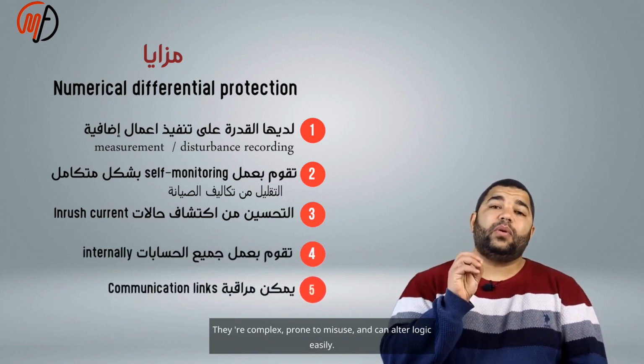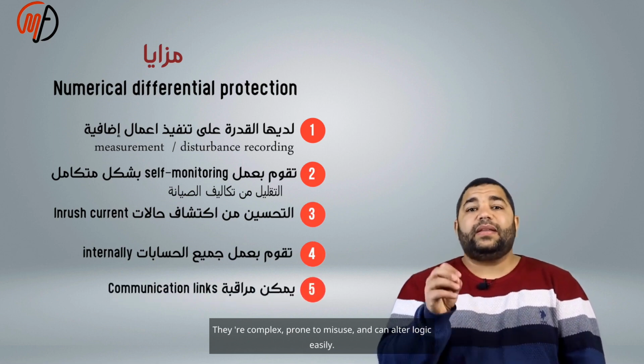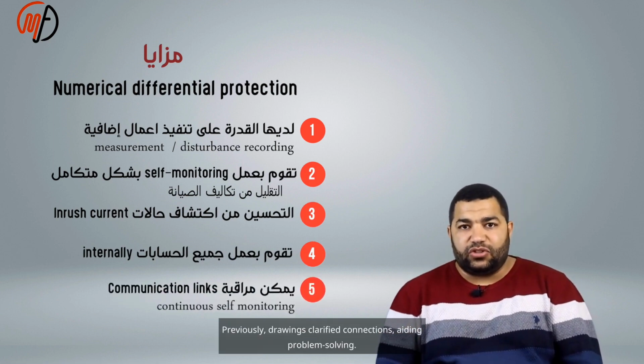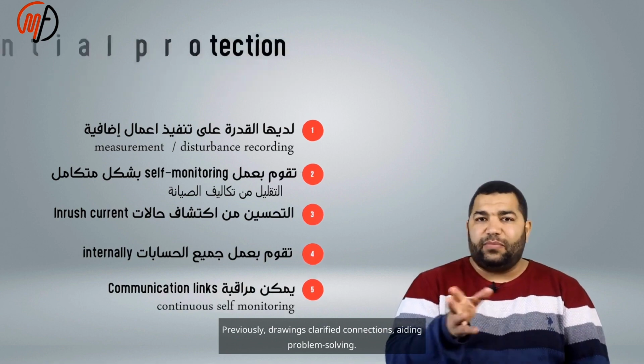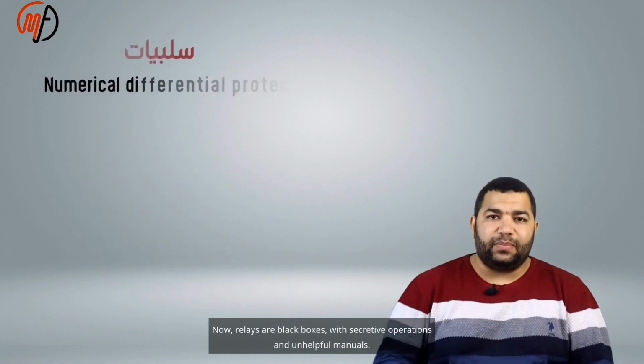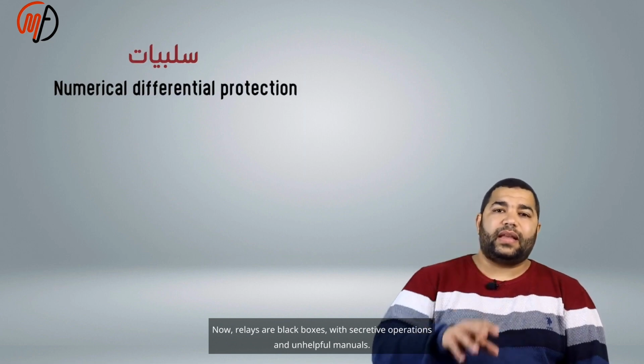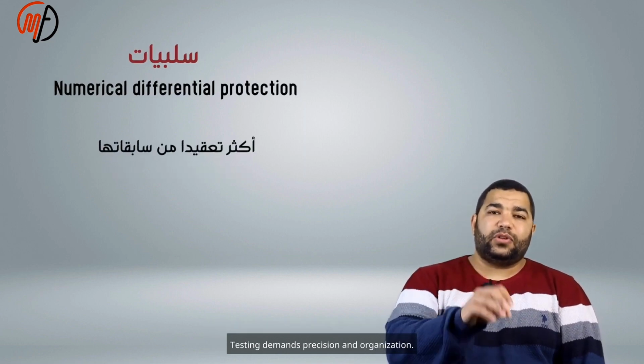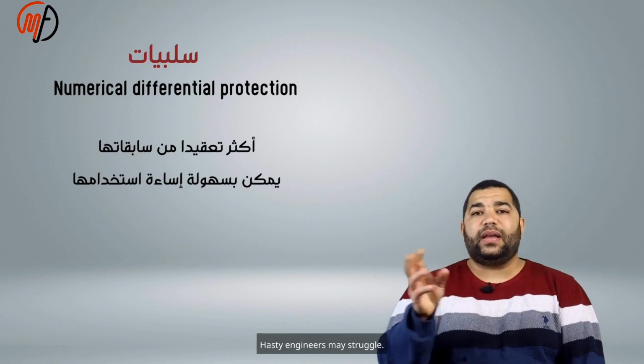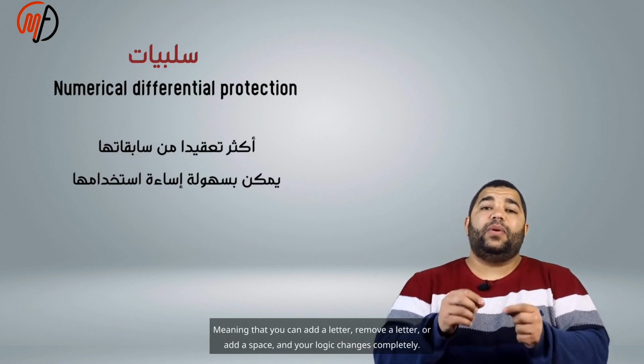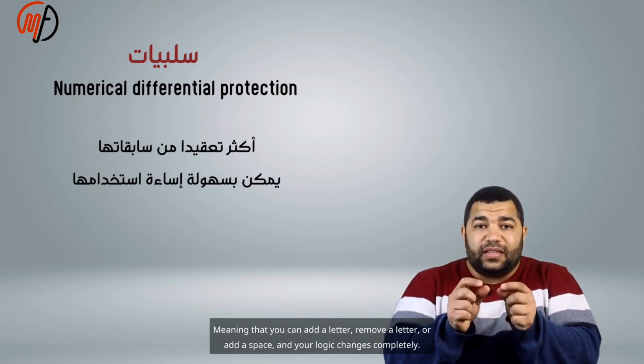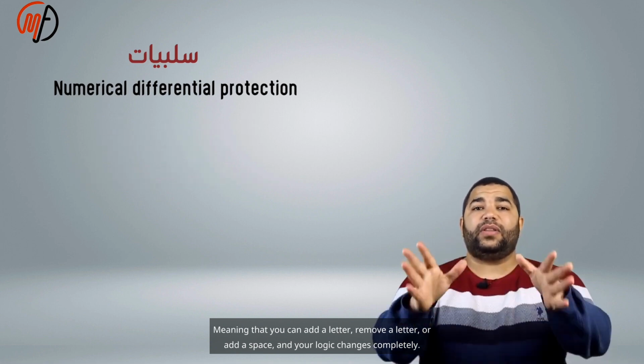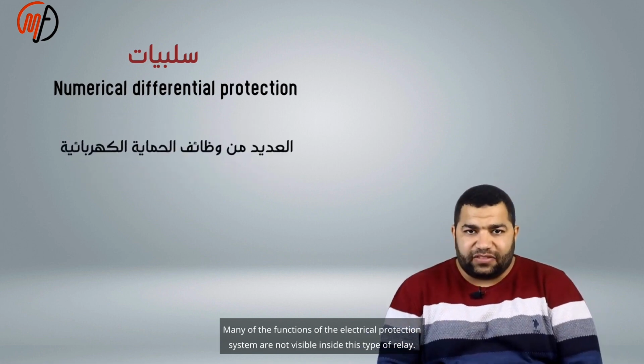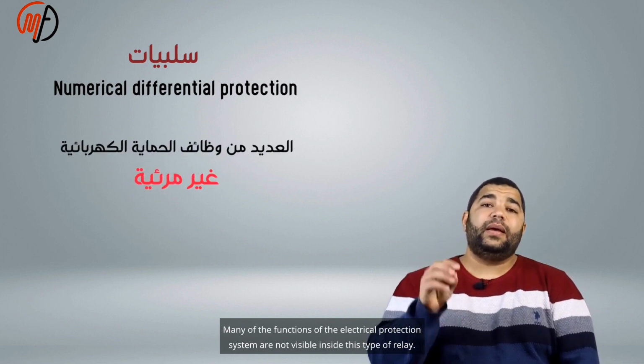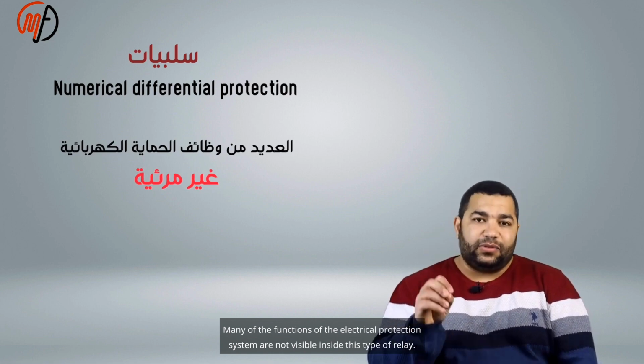They're complex, prone to misuse, and can alter logic easily. Many functions are hidden. Previously, drawings clarified connections, aiding problem solving. Now, relays are black boxes, with secretive operations and unhelpful manuals. Testing demands precision and organization. Hasty engineers may struggle. Meaning that you can add a letter, remove a letter, or add a space, and your logic changes completely. Many of the functions of the electrical protection system are not visible inside this type of relay.